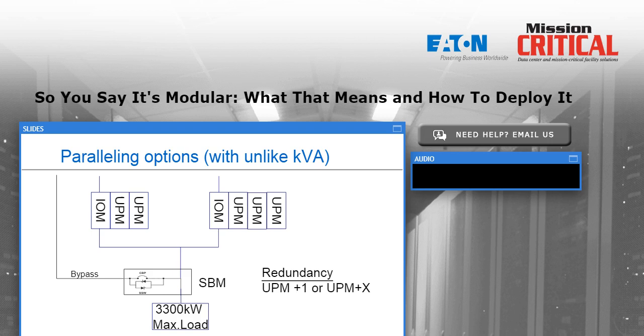For example, the powers that be decide that maybe they want to consolidate the Chicago and the St. Louis data centers in this one facility, so they need a lot more power and they need it right now. No time to rip it all out and start over again with a bigger UPS system. So what they do is they bring in a second UPS that's bigger than the first UPS. You'll notice the one on the right has 3 UPMs. That's a 900 kilowatt UPS paralleled with a 600 kilowatt UPS.